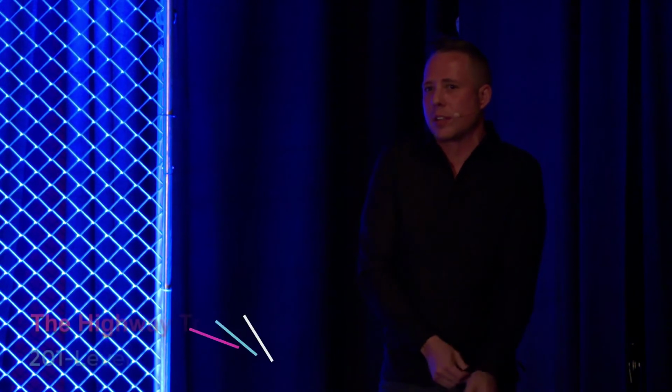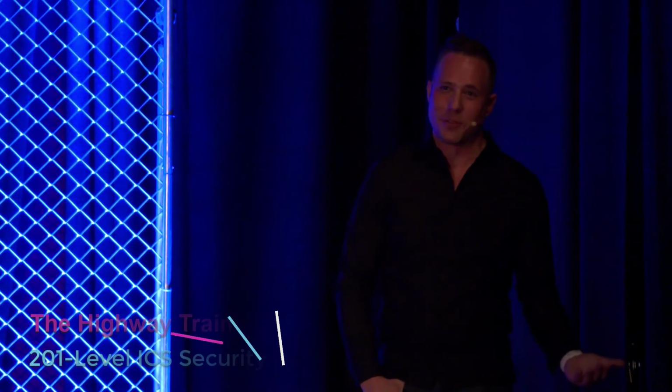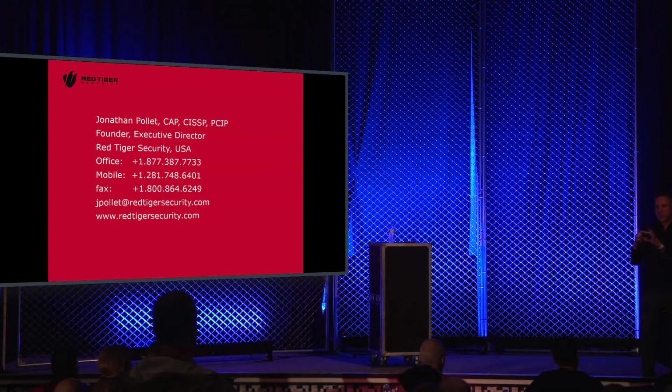You are going to tax the switch with a little bit more work because it has to copy every port over to the mirrored port. But most switches, if they were bought within the past 10 years, are no problem. However, some of these plants have switches that are 30, 40 years old, or that may not support a mirrored port. We like to use a Throwing Star LAN tap. It's unpowered and has four different connections on it. You're going to have to break the connection for about 2 seconds. There's going to be a drop in traffic as you pull that uplink port, plug the tap in, and then put your laptop in the tap.